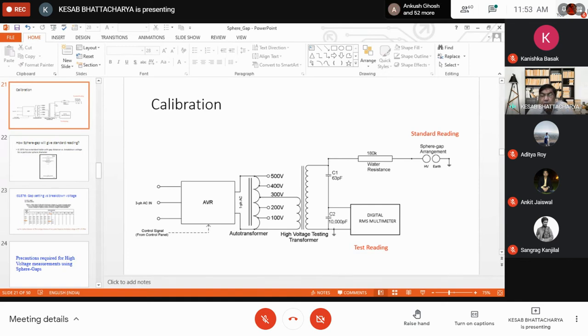Therefore, in the IS specification, it has been mentioned that under two definite conditions, you must make some arrangement so that the presence of an electron within the gap is ensured, and the process is called irradiation, irradiating the gap. What does it mean by the term irradiation? It means you have to supply electrons externally. There are many ways. One such way is you may put UV capsules within the gap, or even you can have a third electrode firing arrangement.